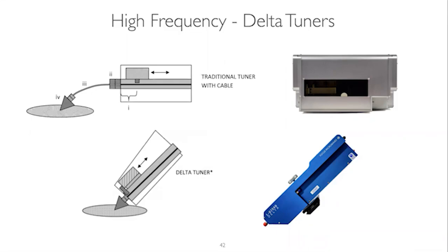So a few years ago, we came up with what we call our delta tuners. We took the guts of the tuner and put them in a miniaturized version, so you could connect the tuner directly to the probe tip. This has significant advantages in terms of insertion loss, and the tuning range is great at this point. We could easily reach 0.85 gammas at 28 gigahertz, not only at the fundamental but also the harmonics.